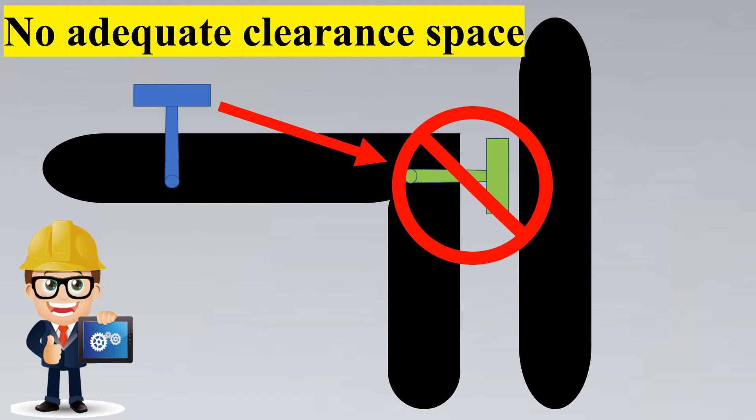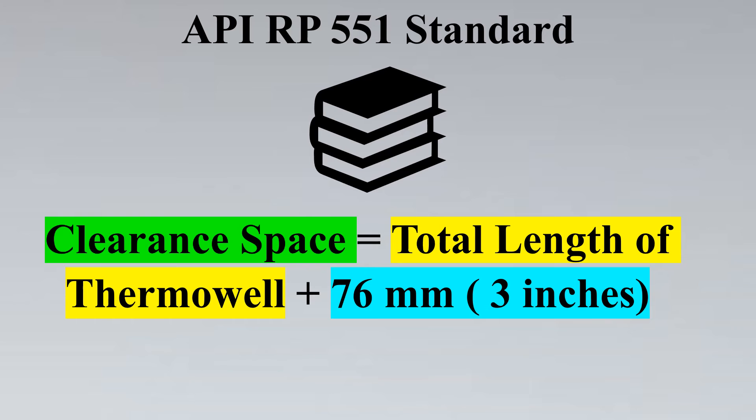We should not follow such places where there is absolutely no place to remove the thermowell out. But you would have the next question as to what should be the clearance space? How much clearance space should we give? For this one of my most recommended practice that I personally find very valuable is API RP 551 standard and this standard states that the clearance space should be total length of the thermowell plus 76 mm or 3 inches. So a little bit of safety margin added so you can remove the entire length of thermowell outside. If you want to dig deep into it, here is the page number which is page number 25 of API RP 551 where you can dig deep into the standard.